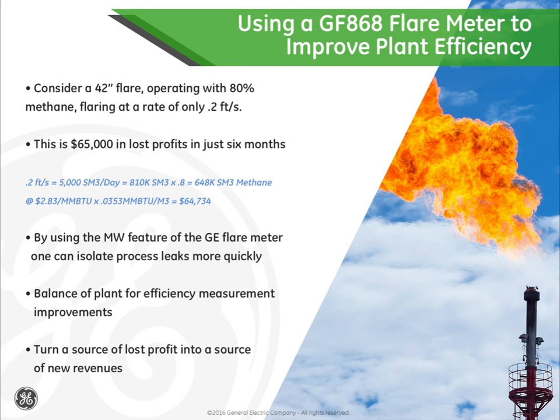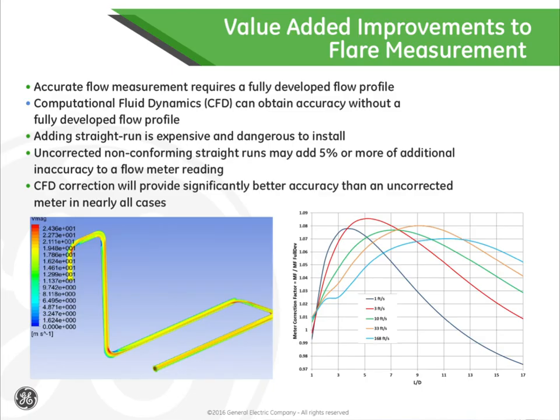Okay, accurate flow measurement requires a fully developed flow profile. Dan touched on this a little earlier. Traditionally, this is obtained by the requirement of having 20D upstream, or 20 diameters of piping upstream of the meter. Recognizing the challenges associated with limited straight run availability at many refineries, GE has embarked on a comprehensive multi-year study to quantify pipe bend effects on flow profiles under a wide range of conditions. By employing computational fluid dynamics, or CFD, required meter accuracy can be achieved without a fully developed flow profile.